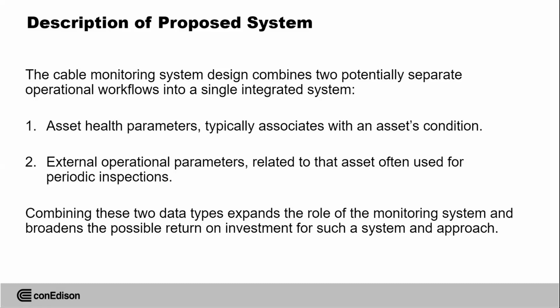So the next question came: how do we describe that system? What is the description of the system we're going to address? The cable monitoring system design combines two potentially separate operational workflows into a single integrated system. So we try to address two in one. From one side, asset health parameters typically associated with asset condition, for example, temperature, for example, partial discharge, or the current in the sheath.